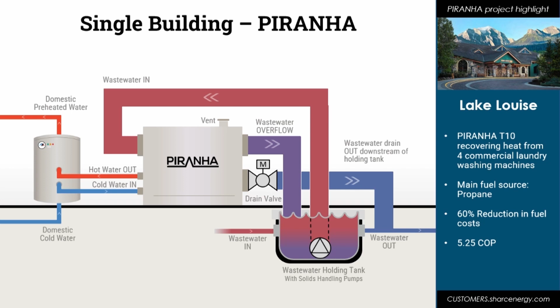And I've got a little example from Lake Louise. It's a hotel in the Canadian Rockies. We're supporting 4 commercial laundries, and basically we've cut their energy costs by 60% just by using the hot water coming out of the laundry machine, running it back through our system to then make hot water for the washing machines. So now the boilers only cycle like every 45 minutes as opposed to every 5 minutes. So massive savings, and they love us up there.